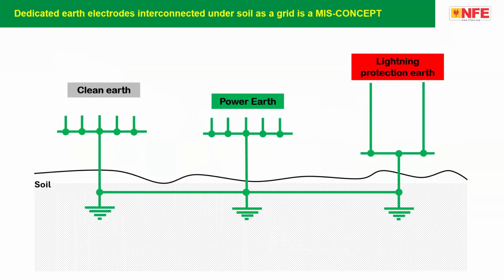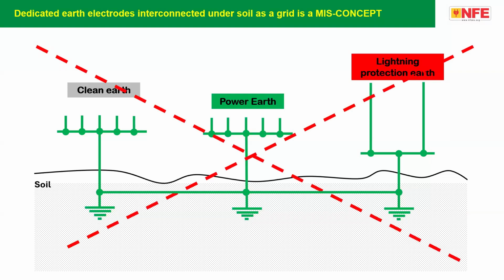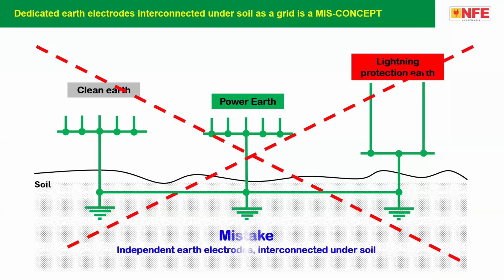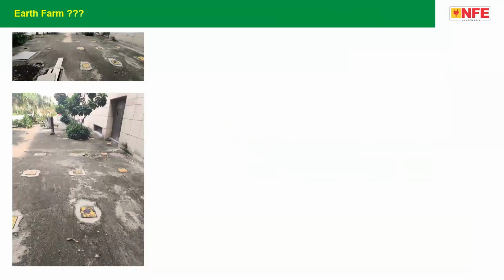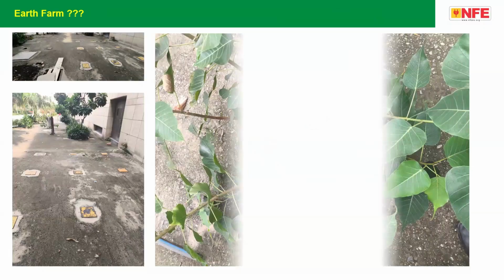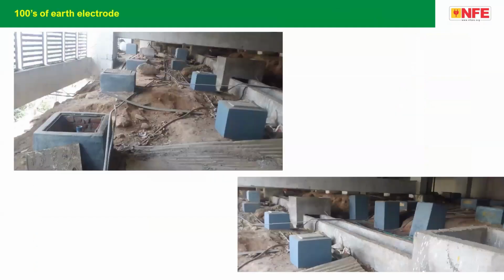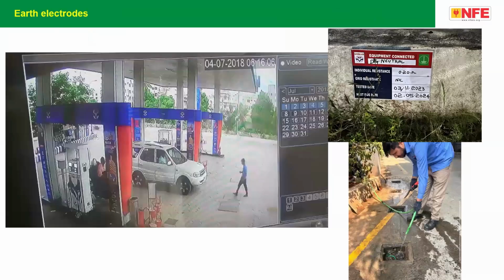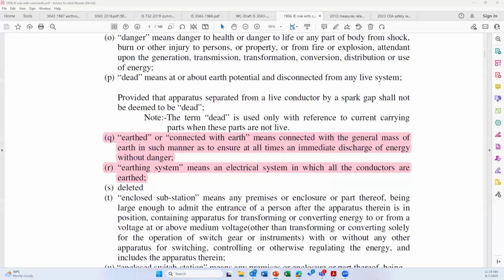The third mistake: sometimes people are very much proud that they interconnected everything under the soil as a grid. This is also wrong. Earthing is not about putting too many earth pits or earth electrodes and connecting everything to the earth electrode. As a result, you can see buildings with an earth farm all around the building, everywhere earth pit, earth pit, earth pit. And finally, there is the practice of putting water into the earth electrode and so on. Predominantly, this was due to the old definition.